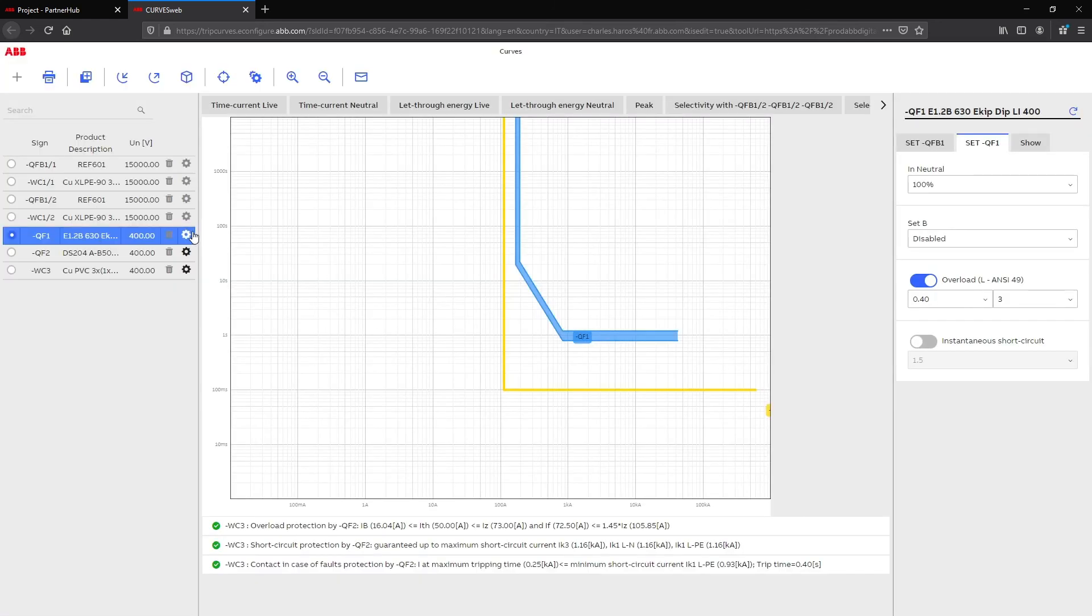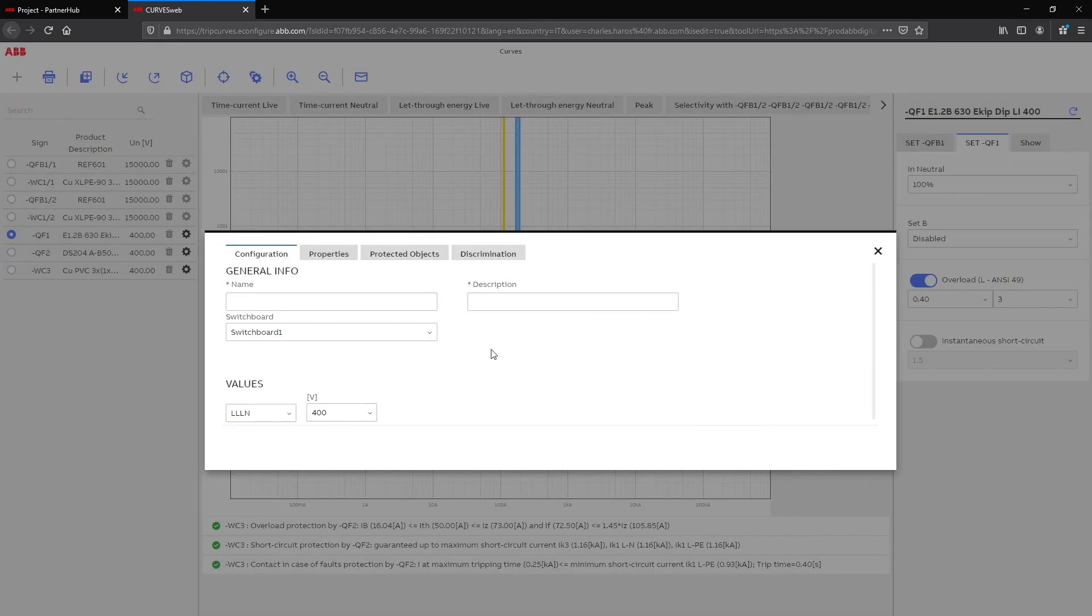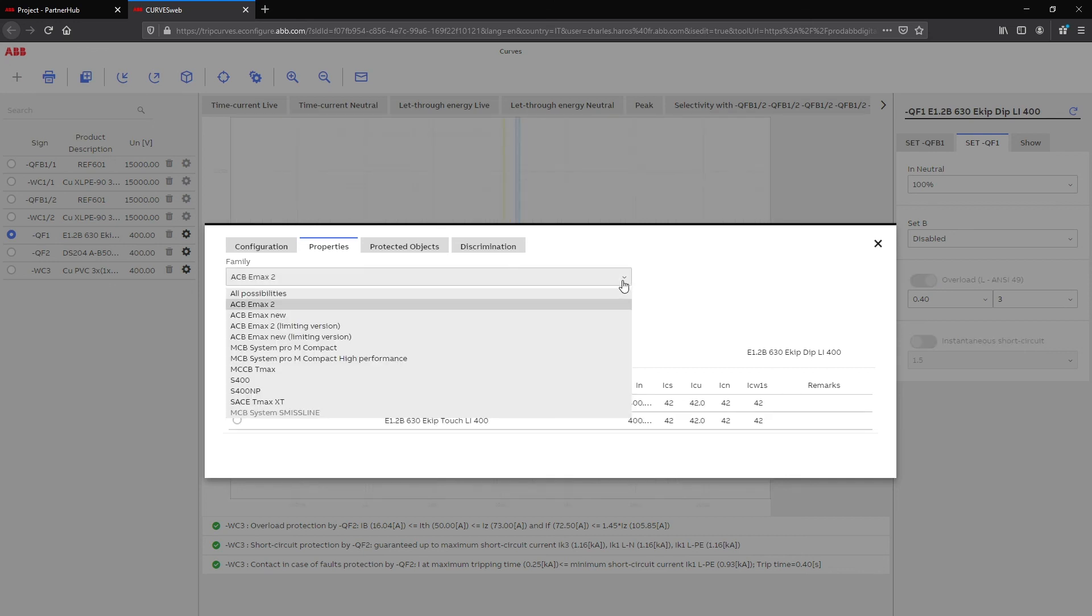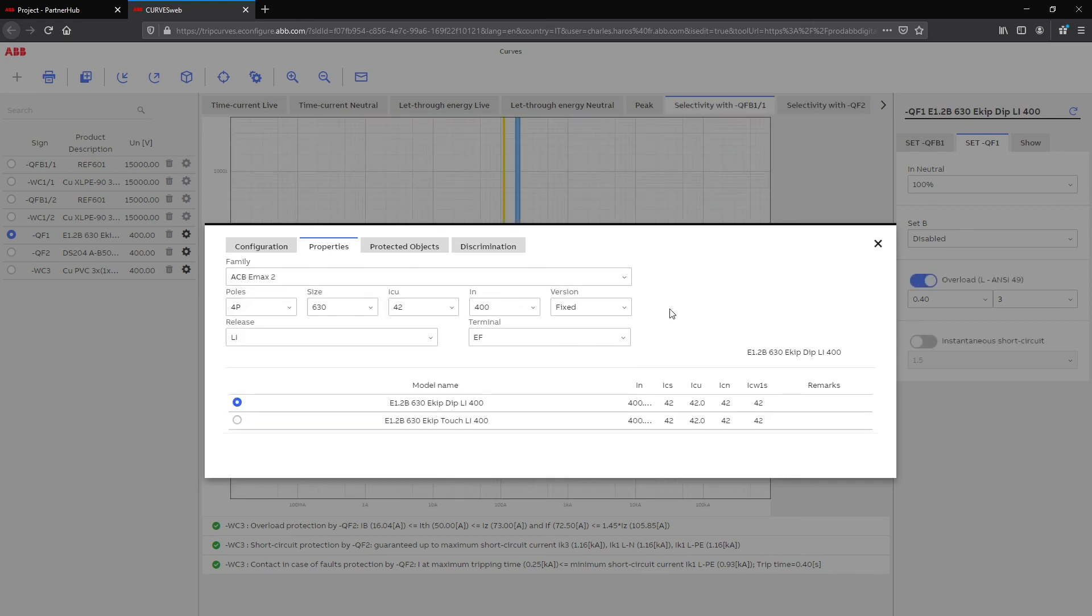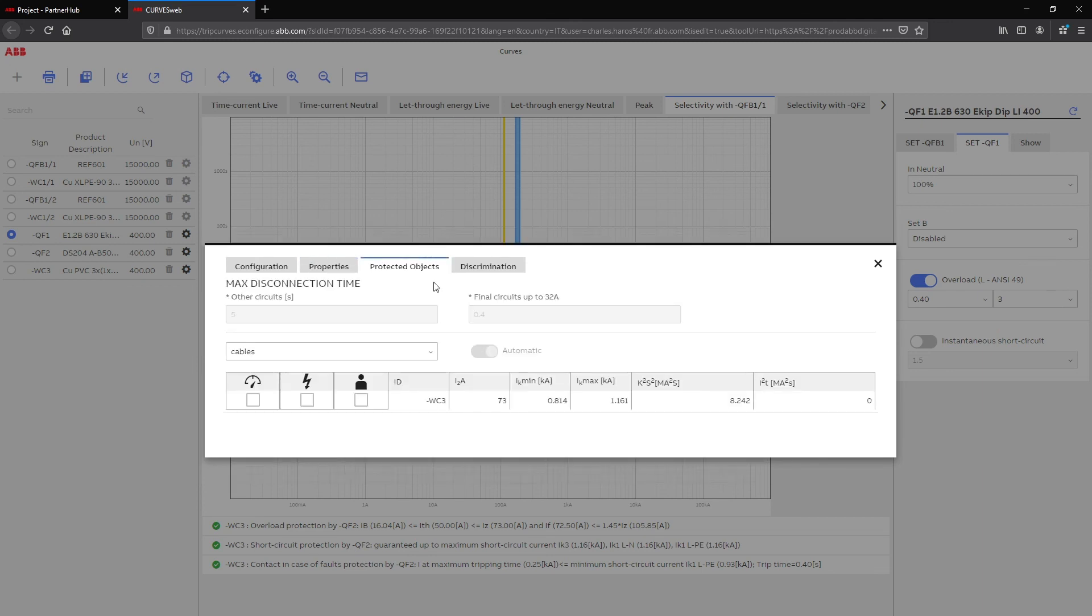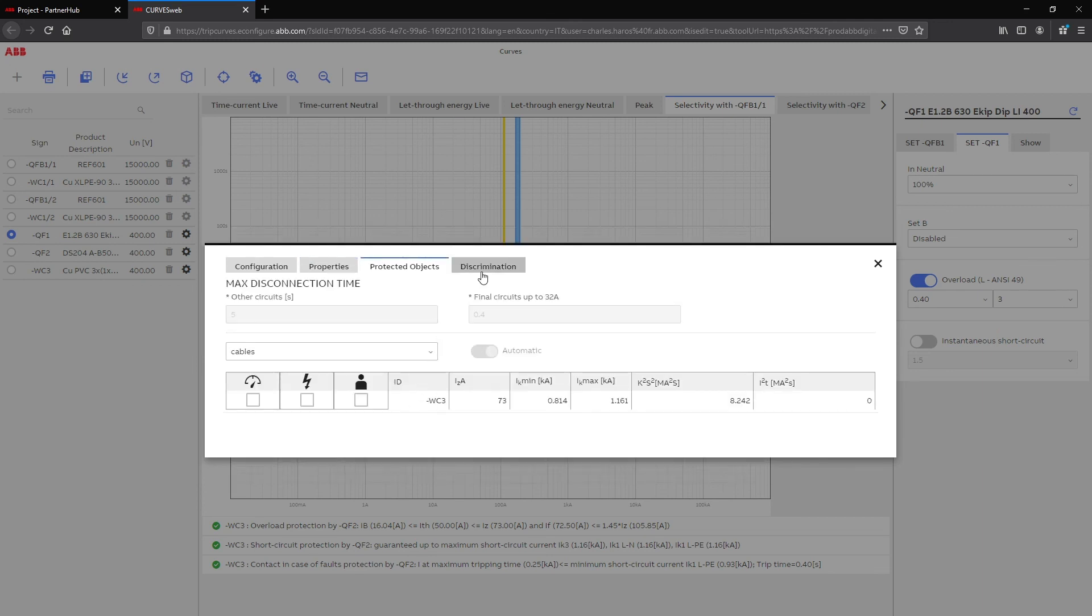The gear icon will open the settings window for a selected device. From this window, you can replace the selected device with another one, set what objects the device is protecting from overload, short circuit, or indirect touch, and set the selectivity or backup relation with other devices.